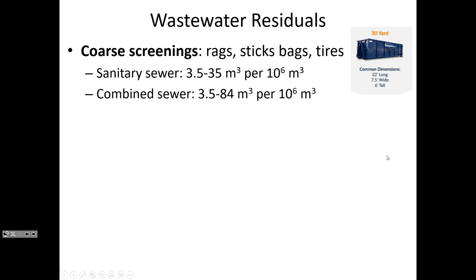There are a lot of different categories of things we have to dispose of besides the purified water. What came into the treatment plant was a mixture of solids, grit, fats, oil, protein, water, nutrients like phosphorus and nitrogen, and even some toxic pollutants — organic and metals. The whole point of wastewater treatment is to take this mixture, separate it, and ameliorate the pollution by, for example, reducing the BOD or digesting fats, then discharging certain things to the receiving water like a river or lake.